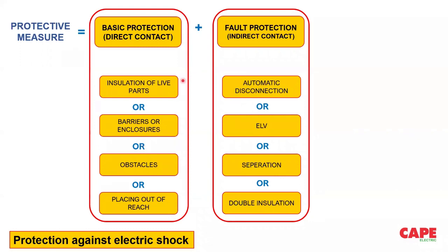Generally, the measure which we use for basic protection is insulation of live parts or barrier or enclosure inside a low voltage consumer premise, and for fault protection, automatic disconnection or extra low voltage. These two are made. Of course, separation is also made in some cases. So the first job of the auditor is to understand these safety measures and their application, and he has to find out the applicable safety measure for a given location. Location to location, it varies.